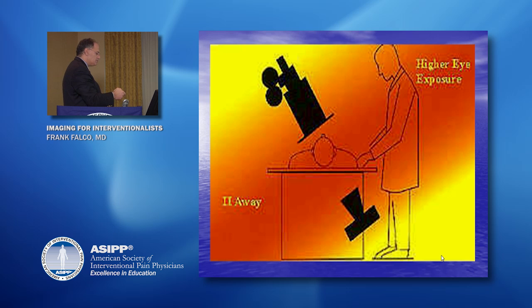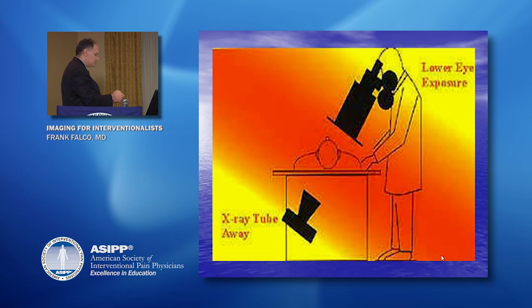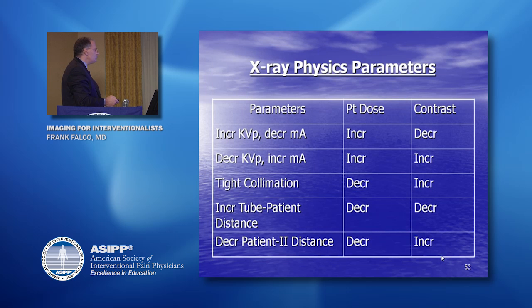Now, the opposite is true. If we turn it this way, so the X-ray tube is away from the physician, the scatter is in this direction, more of it going towards the feet, and you're getting lower eye exposure. So the positioning of the C-arm certainly impacts not only the characteristics of the scatter, but what areas are going to be affected by that scatter because of the change in orientation.